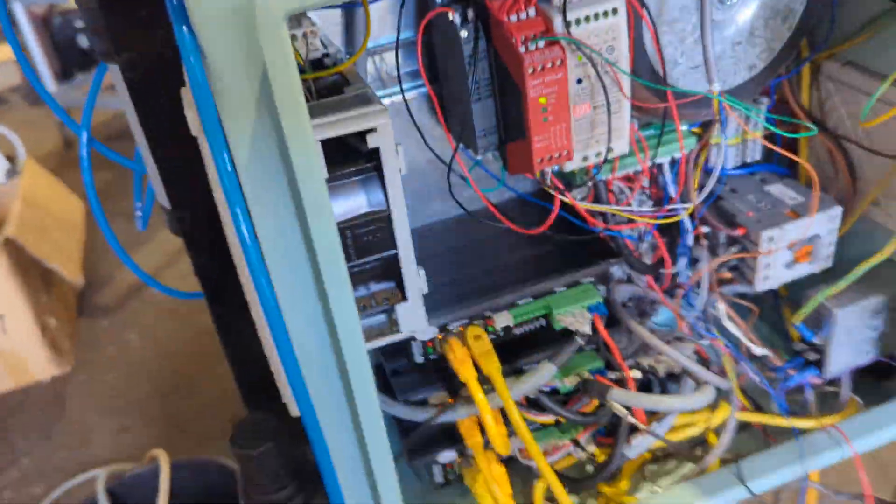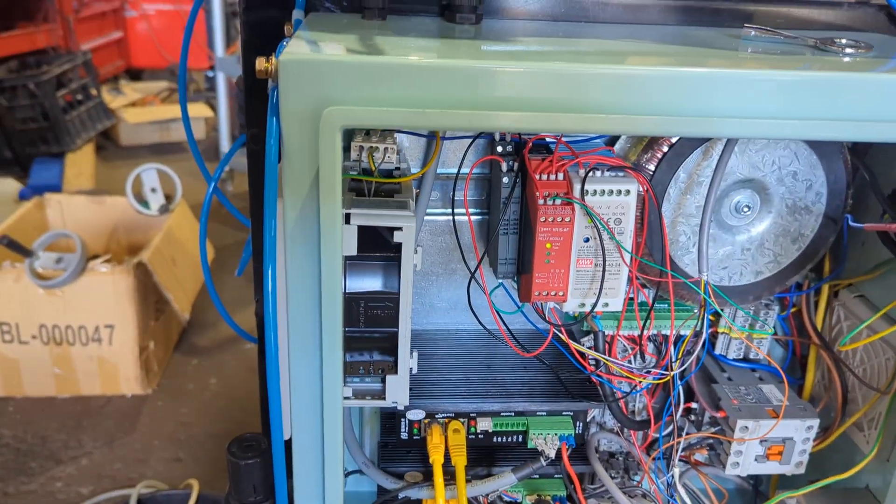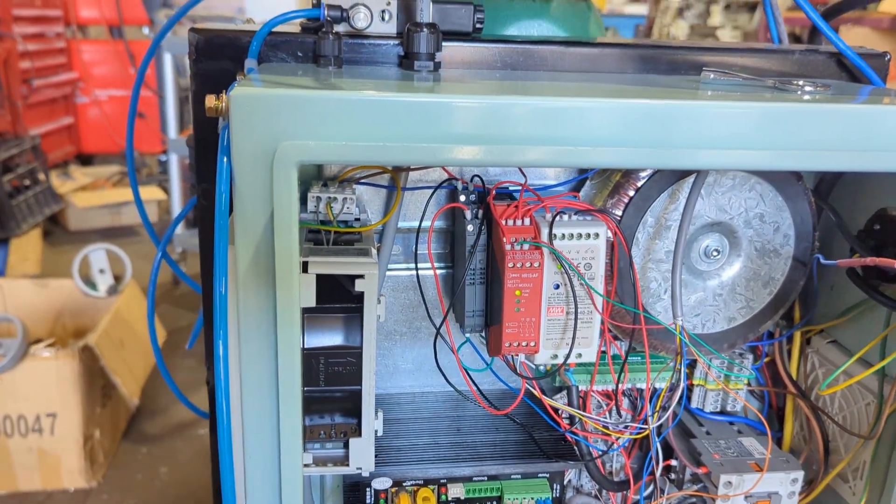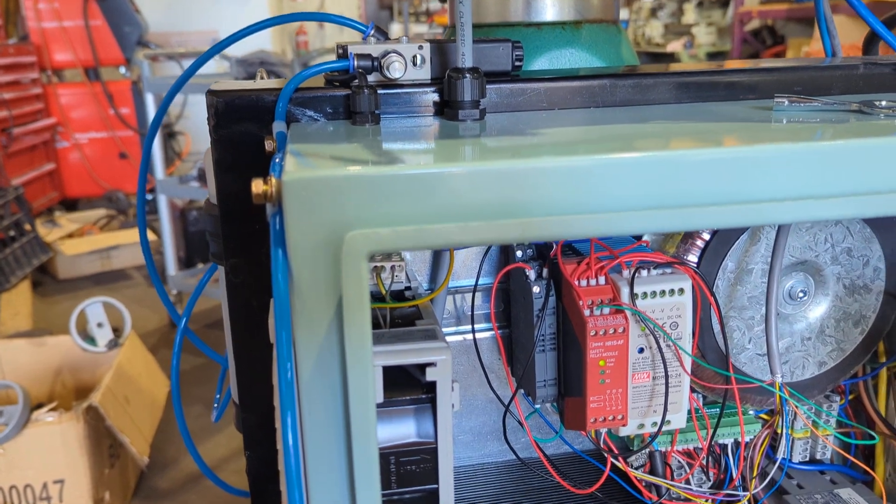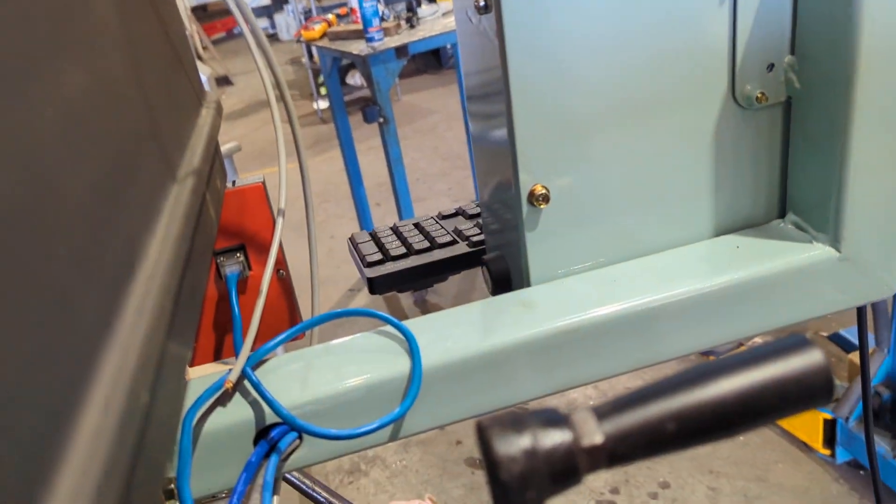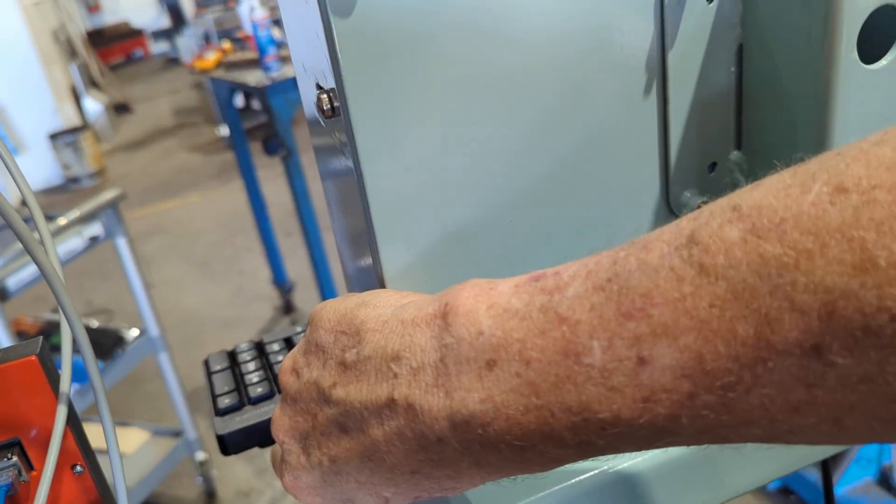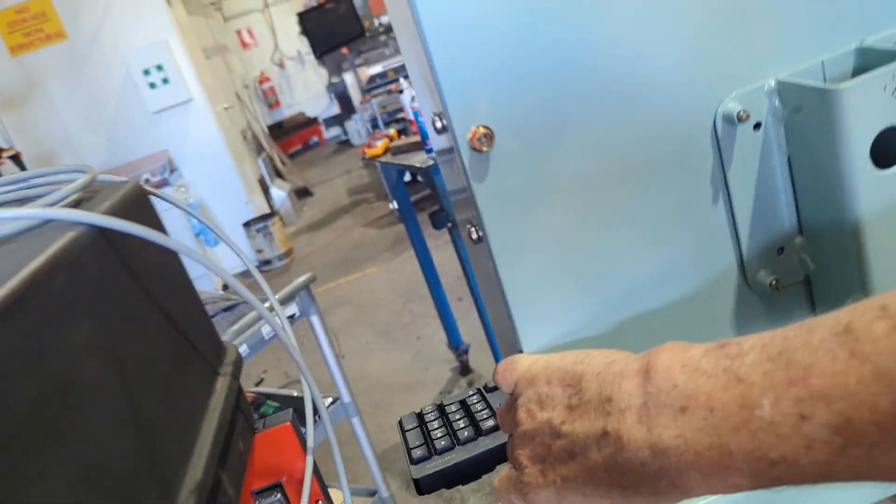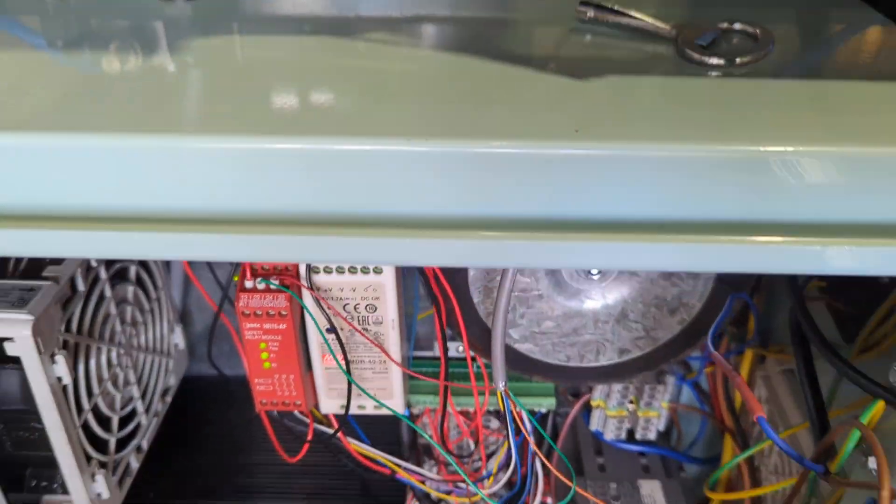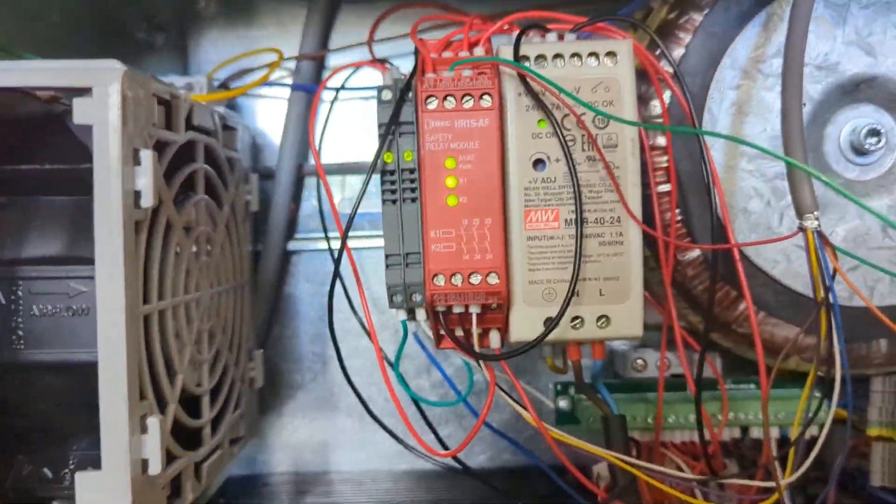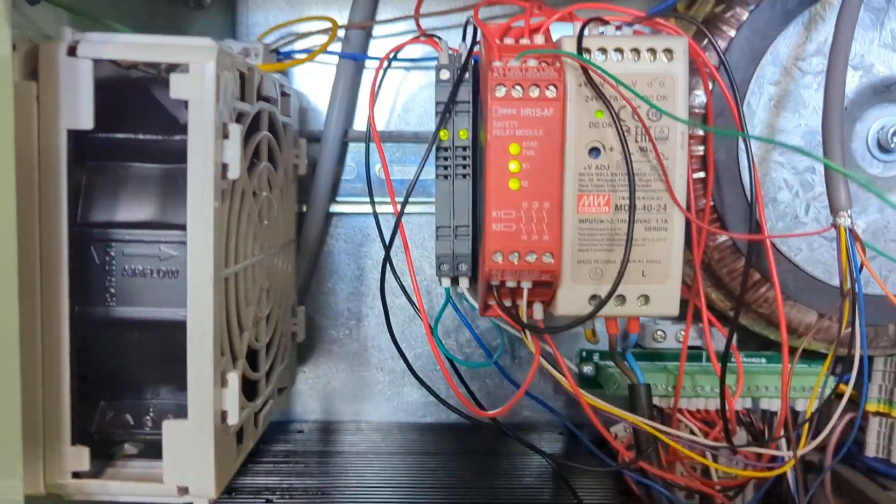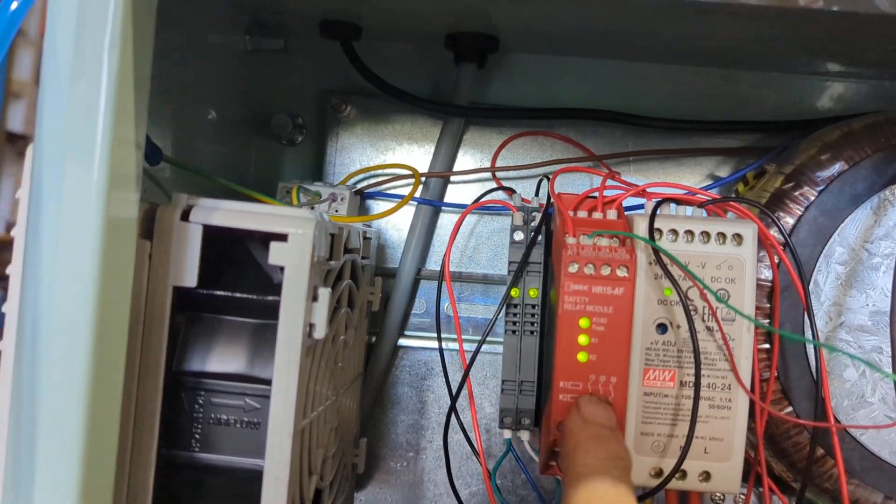The remaining IO to do is e-stop the three drives and also I need to bring input from the safety relay back into Linux CNC. So if we just go up here and go around to our safety reset, I'll just make sure the e-stop's triggered, I'll trigger the safety relay here and we should see something come into action. I won't go into the safety relay at this point in time, but the long and the short of it is that there's a lot of fail-safe stuff here and there's three contactors here which are internal which have all come on.